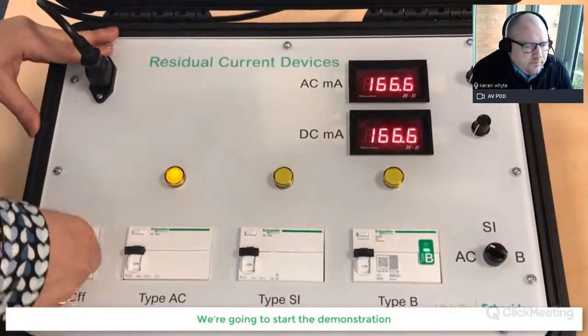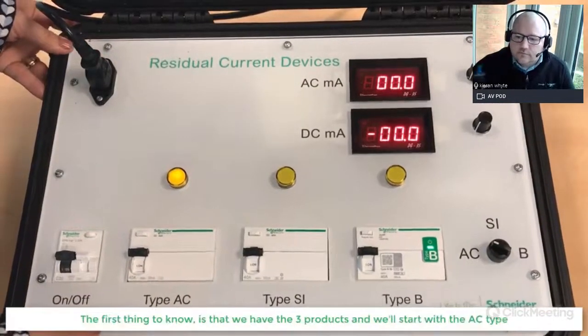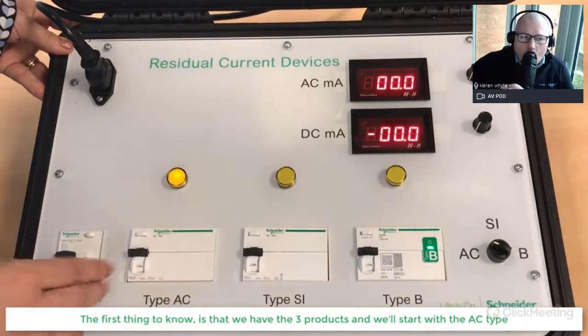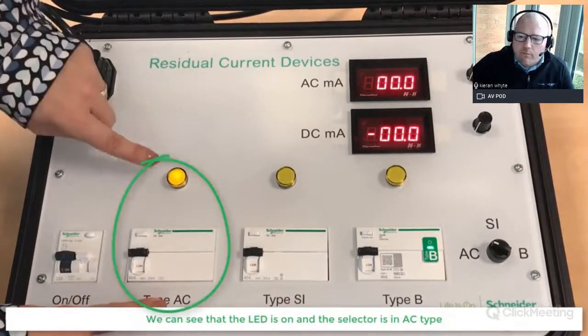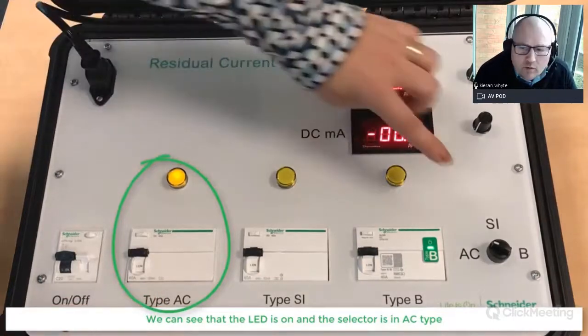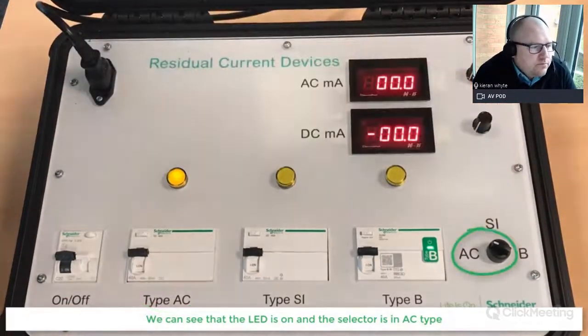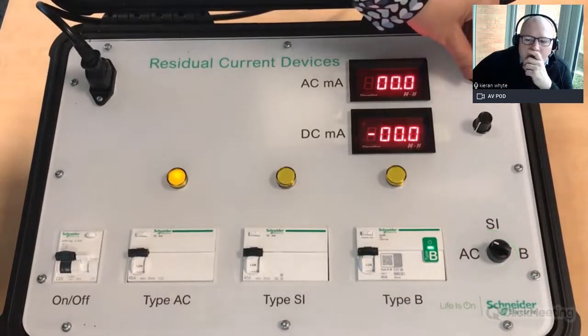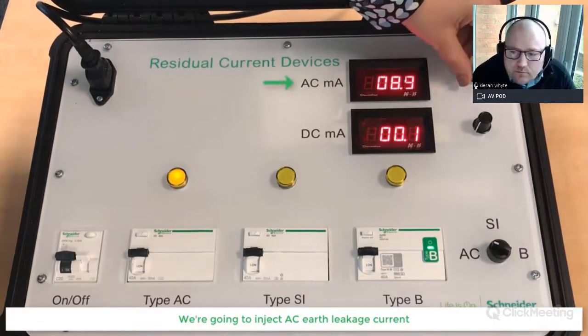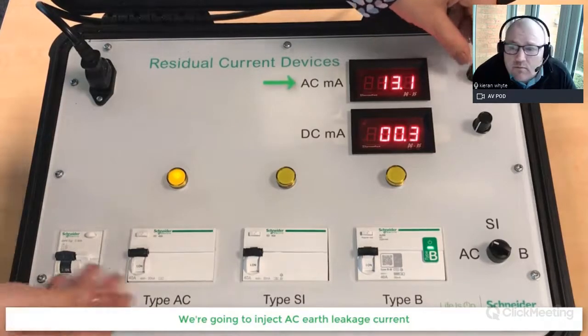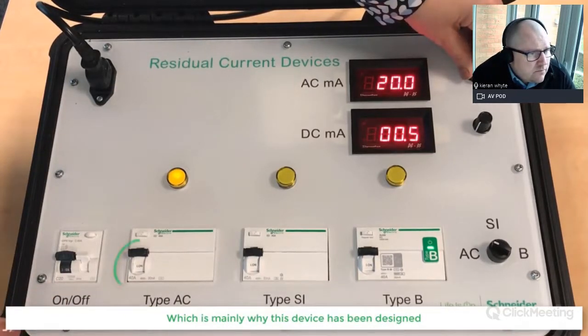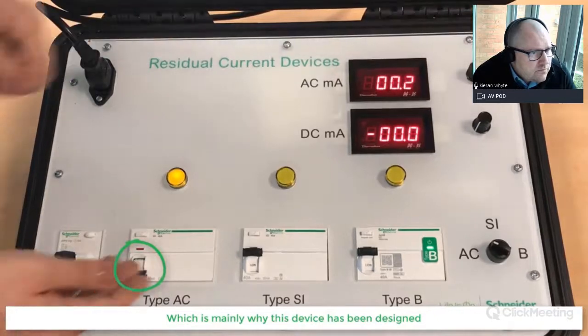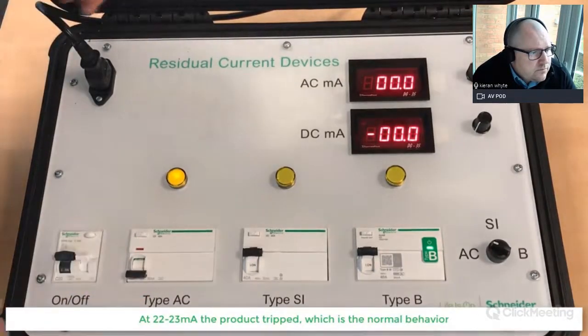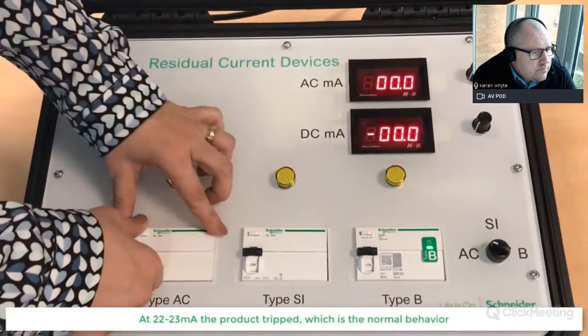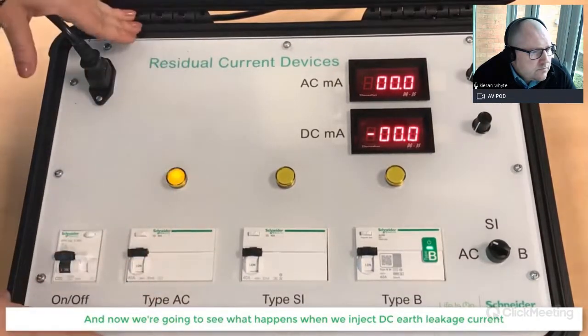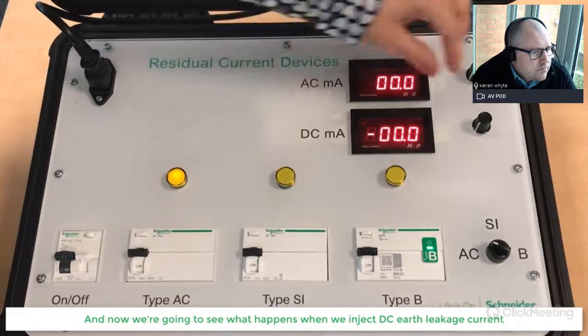So we're going to start the demonstration. The first thing you have to know is that we have the three products, and we're going to start with the AC type. Then we can see that the LED is on and the selector is in AC type. We're going to inject AC earth leakage current, which is mainly what this device is designed for. At 22, 23, the product trips, which is the normal behavior. And now we're going to see what happens when we inject DC earth leakage current.